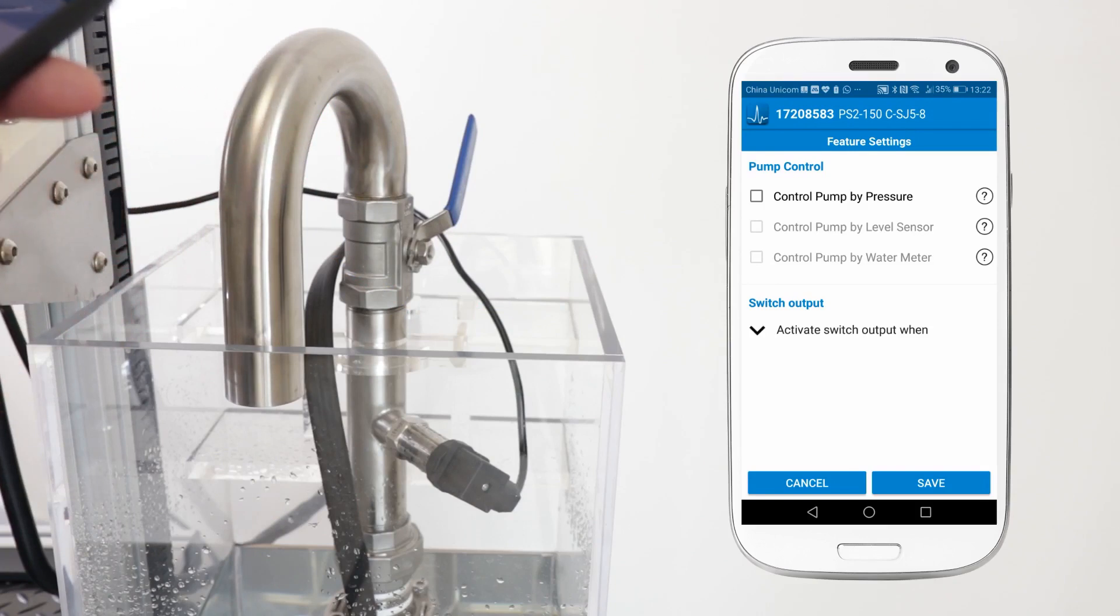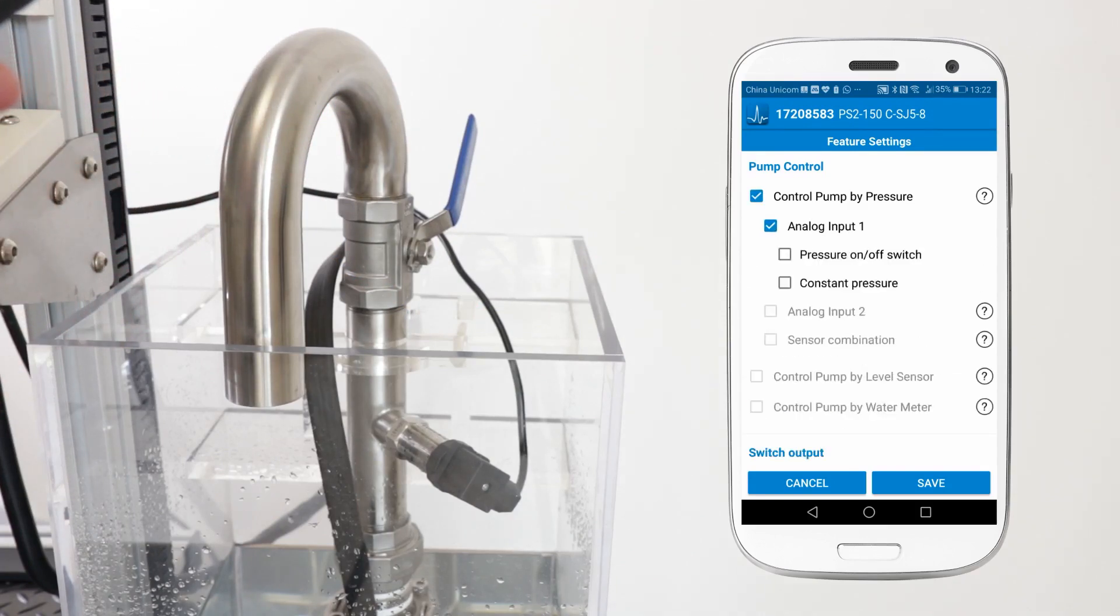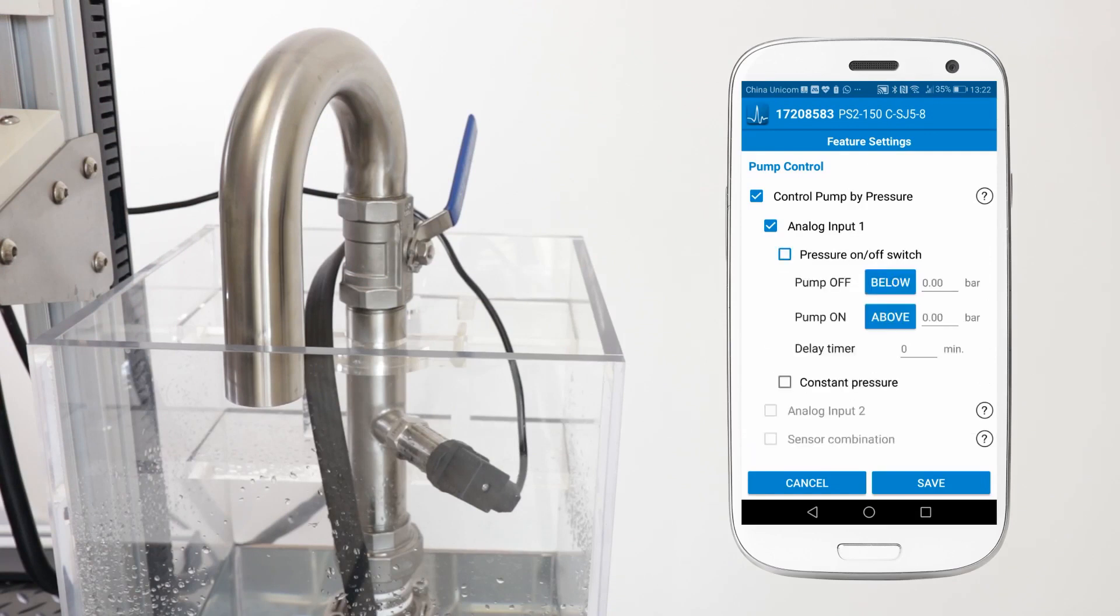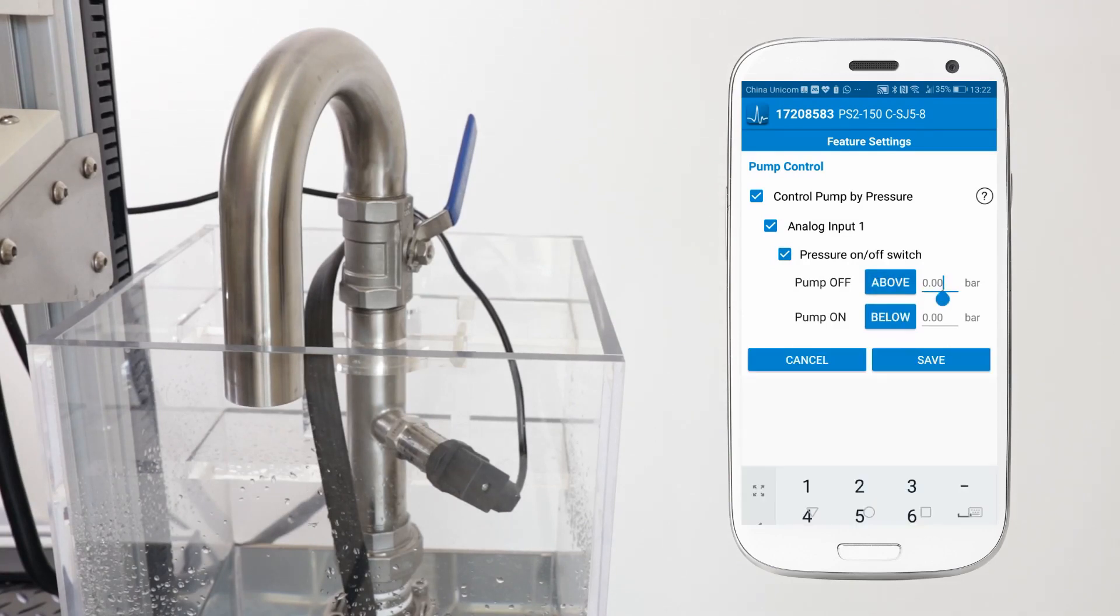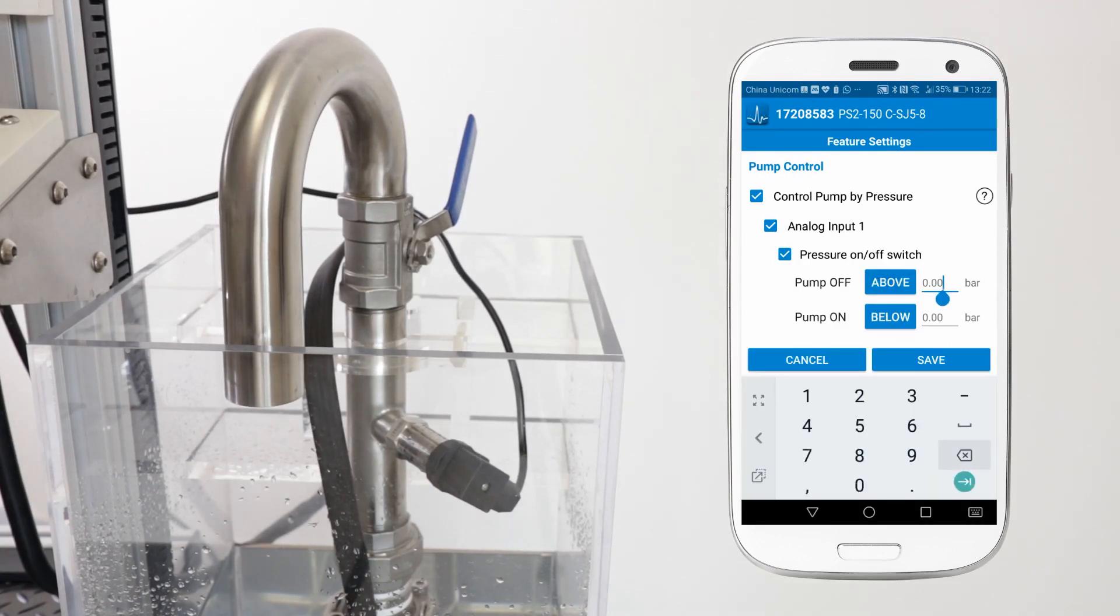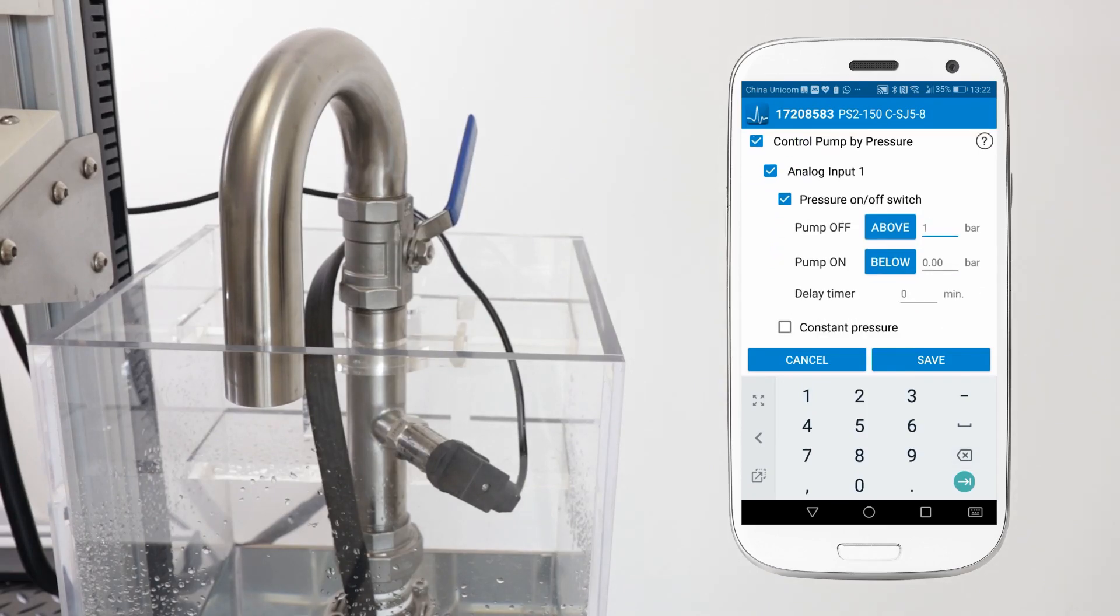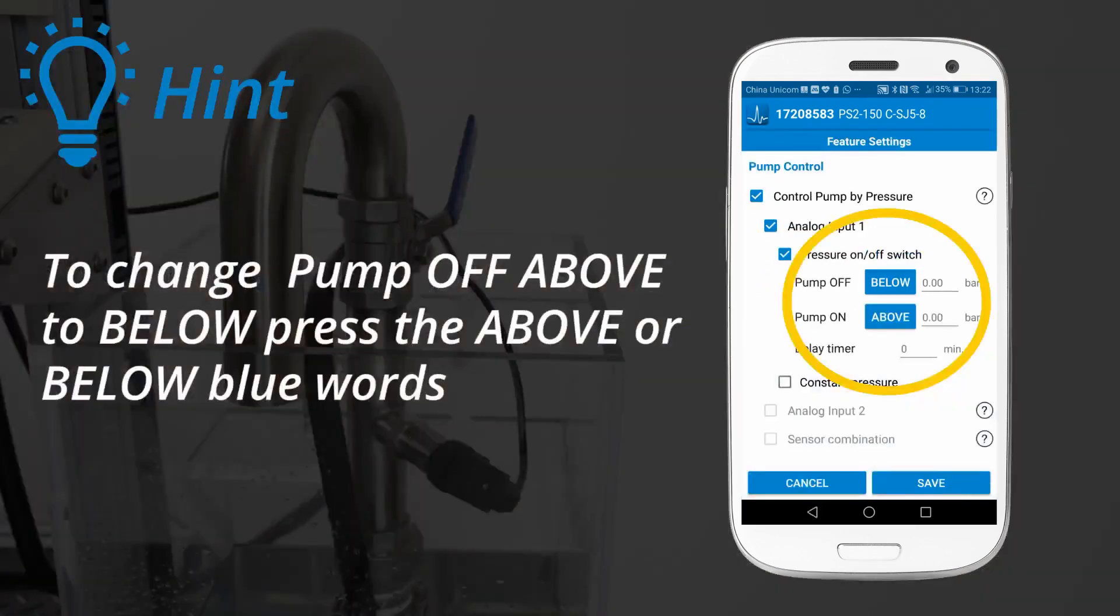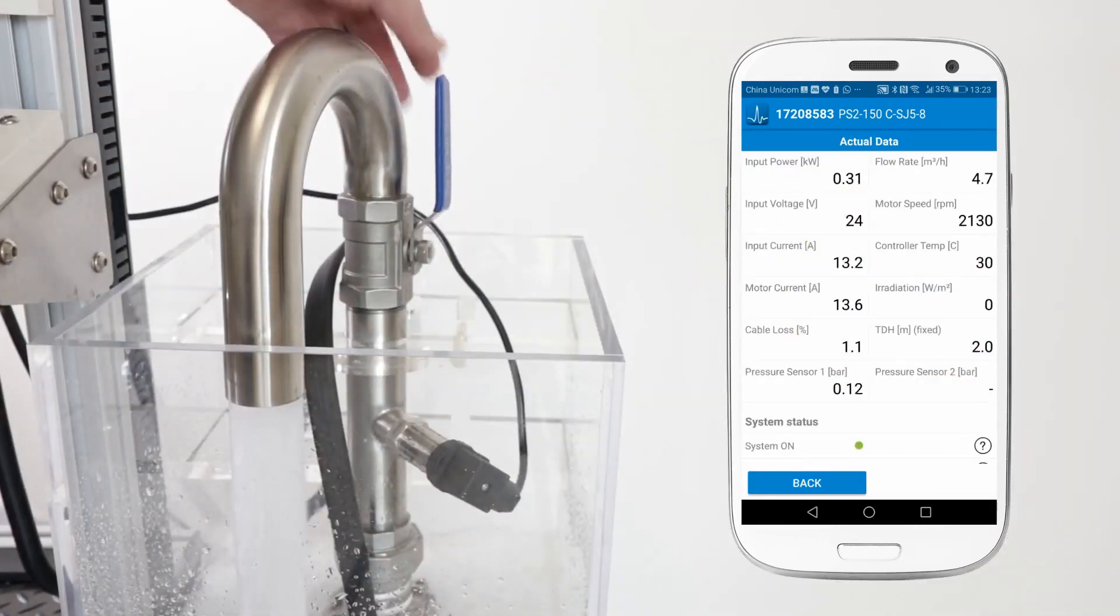To configure this I'll go to the feature settings, select control pump by pressure. This is in bold because we've got a pressure sensor configured. The sensor is on analog 1 again bold and I'll choose pressure on off switch. In our example I want the pump to switch off when the pressure is above 1 bar.